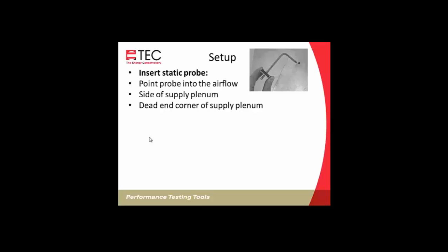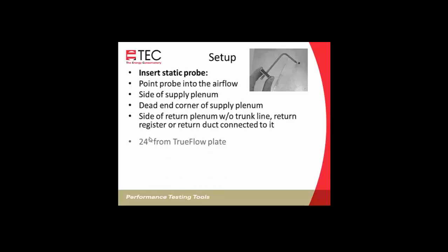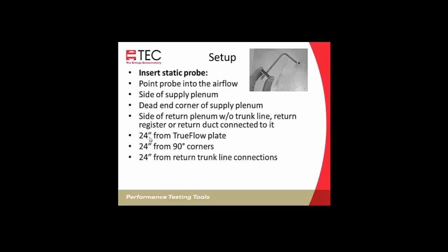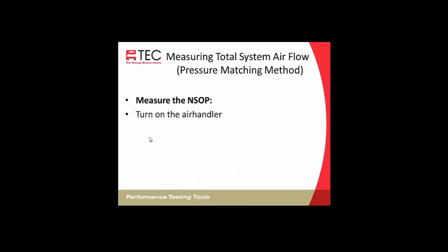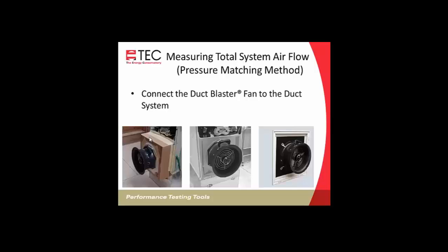And the dead end corner is defined as a corner of the plenum that doesn't have a duct or a trunk or a register within 8 inches of it. You can put it at that location. You can put it at the side of a return plenum without a trunk line return or register duct connected directly to it. You want that static pressure probe to be at least 24 inches from the TrueFlow plate, 24 inches from 90-degree corners, and 24 inches from return trunk line connections. So measure the normal system operating pressure: turn on the air handler, turn on the gauge and write down the normal system operating pressure.